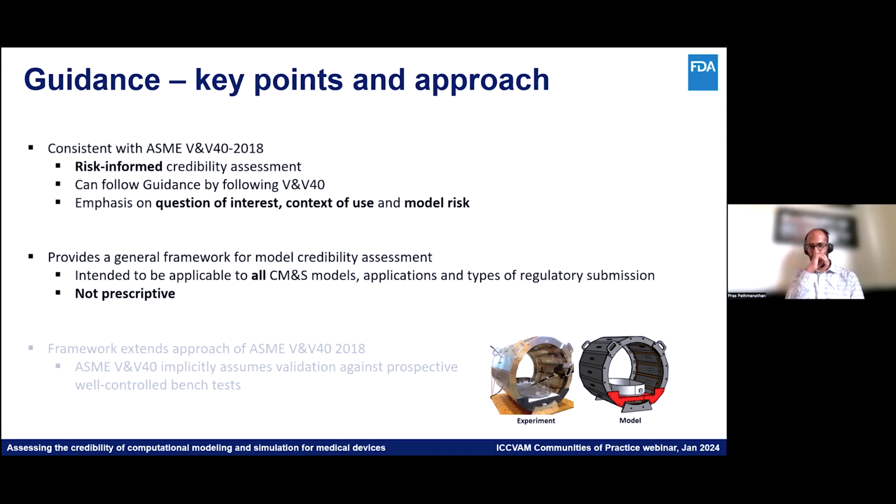So all of those applications that I mentioned in the earlier slide, which had 4 different types of ways of using computational modeling for medical devices. And it's intended to be applicable to any type of regulatory submissions. We have a wide range of possible regulatory submissions, from using models to support the initiation of a clinical trial. Sponsors, manufacturers, have to often provide some data to demonstrate that that's going to be safe, or sufficiently safe, for trial participants, to regulatory submissions for all classes of medical devices, from low risk to high risk. So it's not a prescriptive framework. And it extends the approach of V&V40.